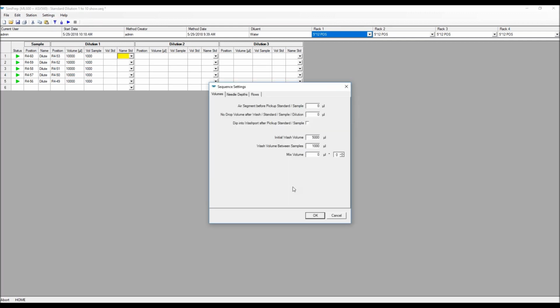And then your sequence settings are what I think really gives the power to the user within the software, because it allows you to essentially add or remove time by adding and removing functions. So I normally recommend having an air segment before the sample pickup, because it does create a separation between your sample and your diluent, and helps with washout and helps to reduce carryover.